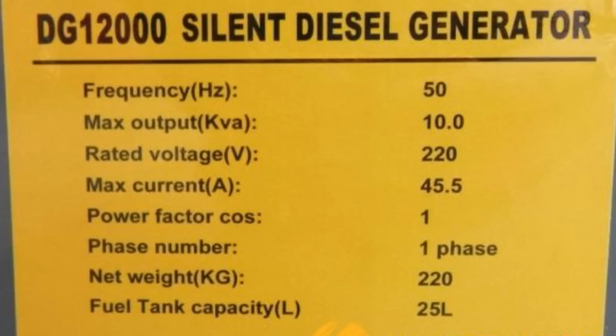Now, I go and look for a similar size generator to buy in a couple of areas of Ghana, and I'm being asked to buy a 10 kVA generator, and the amps was only 26. How? What's going on here? So I try to crack my head to understand what is going on, because if you're buying a 10 kVA generator and it says on the sticker it's only 26 amps, that means in reality 26 amps is about 5.7 kVA.